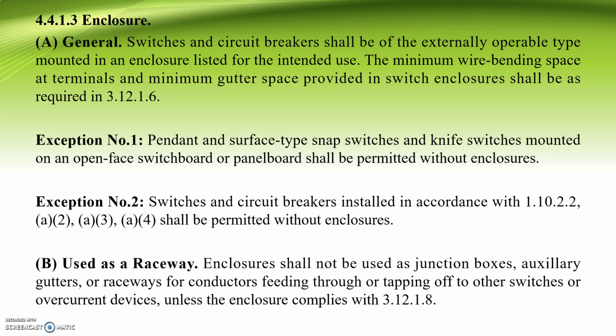So B, use as a raceway. Enclosures shall not be used as a junction box, auxiliary gutters, or raceways for conductors feeding through or tapping off to other switches or overcurrent devices, unless the enclosure complies with 3.12.1.8.